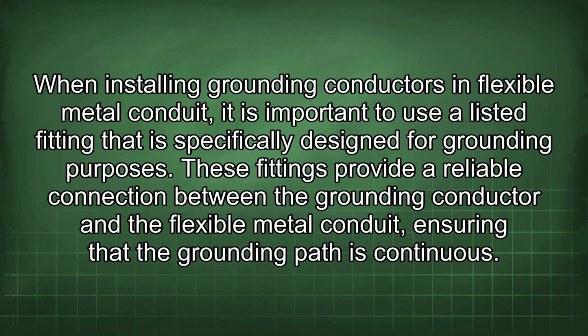When installing grounding conductors in flexible metal conduit, it is important to use a listed fitting that is specifically designed for grounding purposes. These fittings provide a reliable connection between the grounding conductor and the flexible metal conduit, ensuring that the grounding path is continuous.